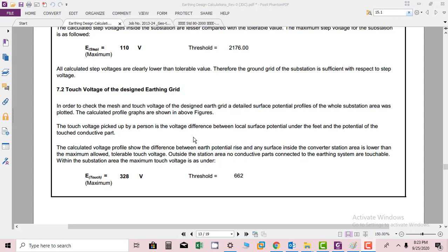The calculated voltage profile shows the difference between earth potential rise and any surface inside the converter station area is lower than the maximum allowed tolerable touch voltage. Outside the station area, no conductive parts connected to the earthing system are touchable. Within the substation area, the maximum touch voltage is acceptable.